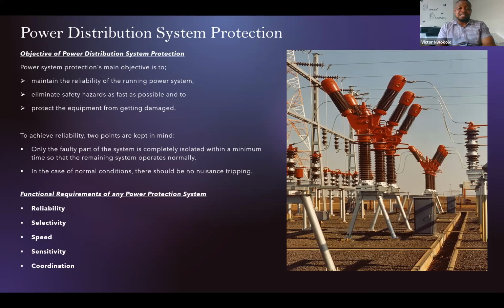So in the sensitivity, it must have enough sensitivity within the design to be able to operate reliably at the correct condition of fault. If, for instance, you're starting a motor, you don't want the power system to operate within 200 seconds as picking it up as overload, or when it exceeds 200 seconds, you don't want your short circuit to kick in. So you must design it correctly so that it's sensitive enough to avoid unnecessary trip.